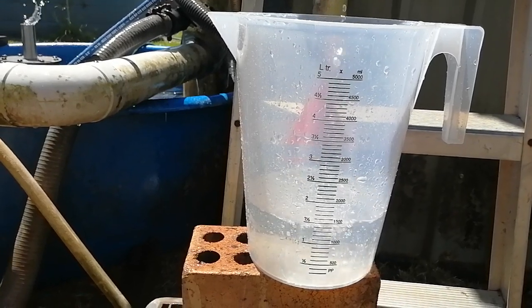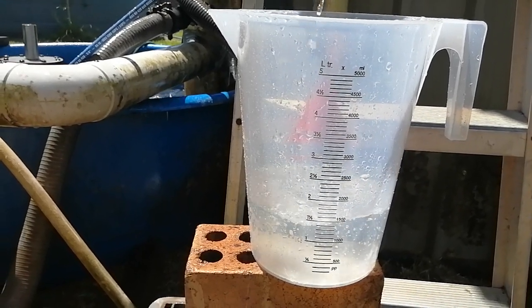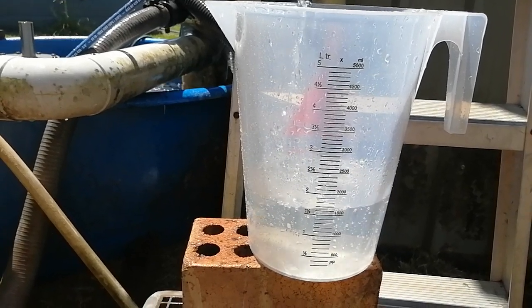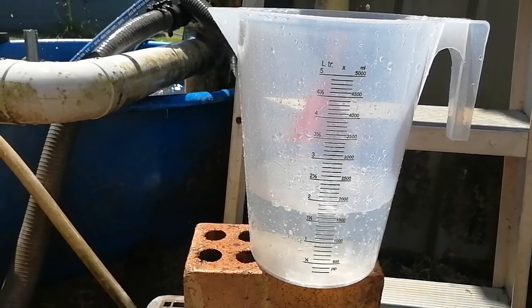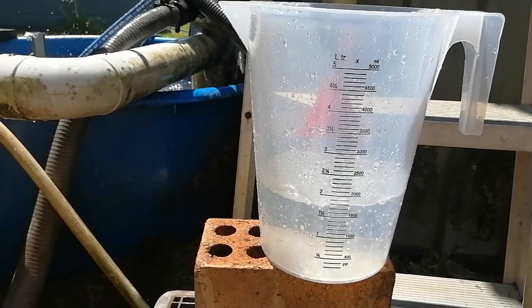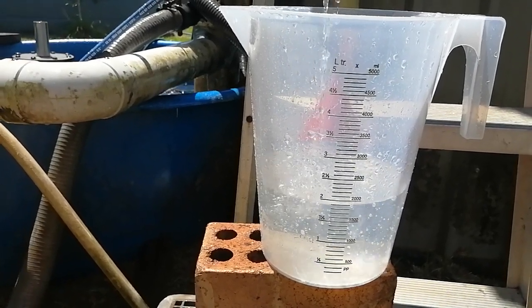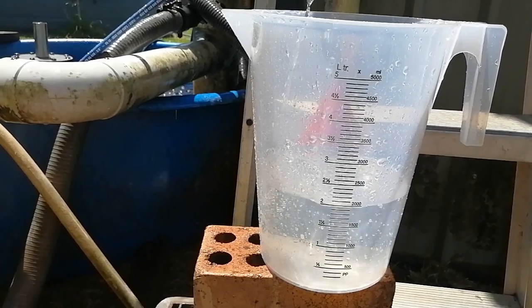So this pump will be working off a 5-metre fall, pumping to a 400-metre head to a village in the Philippines. And we're working off 6 litres a second flow rate, 100mm pipe, hopefully.